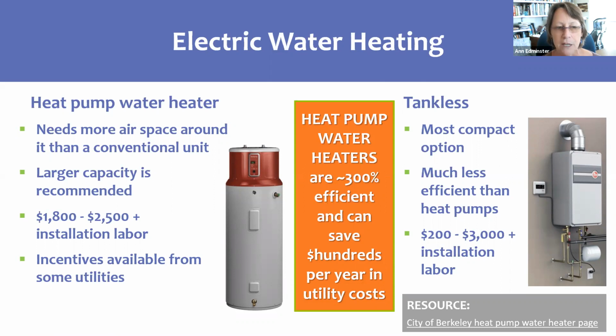The point to be made here is, yes, you can get an electric tankless water heater. I'd say typically the best use for a tankless is where you may have a very small demand, maybe in an accessory dwelling unit or a part of a home that's very distant from all the other hot water draws. So look at that as, in my view, not the go-to option, but more of an okay, we'll consider that when we don't have a great way to incorporate a heat pump water heater option.